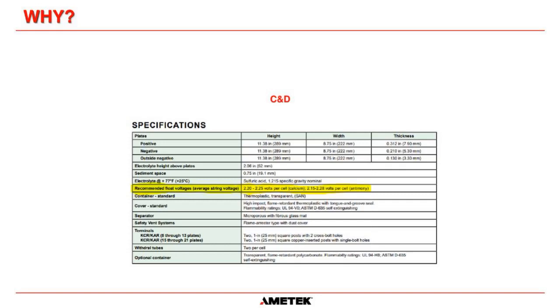My opinion is never. I know that's a very controversial statement. Your batteries should be in a temperature controlled environment. They're gassing, so you have to have a very good AC system to expel that gas and to keep your room in a good temperature. So as long as you set your room temperature at 77 degrees, you never need temperature compensation on a battery.